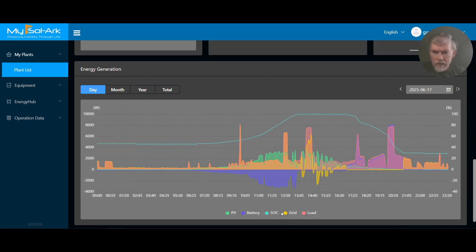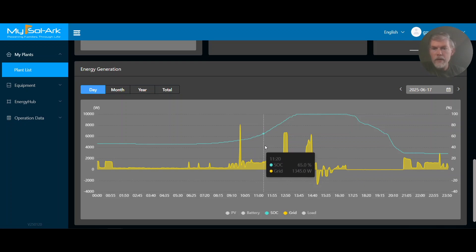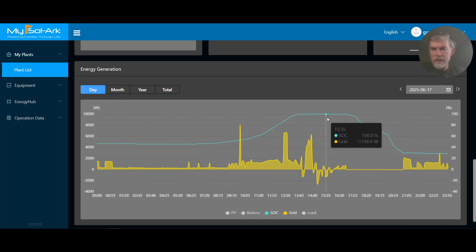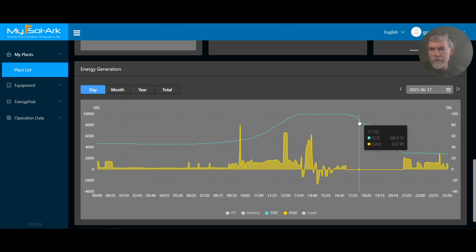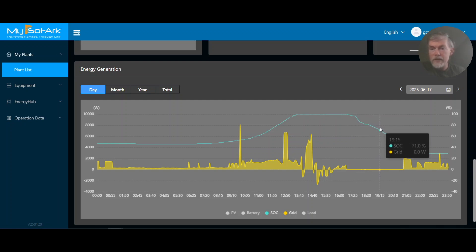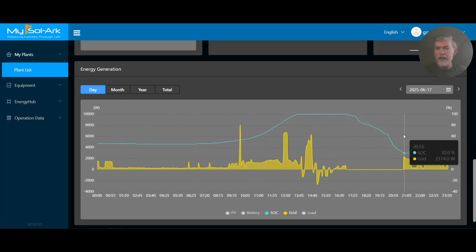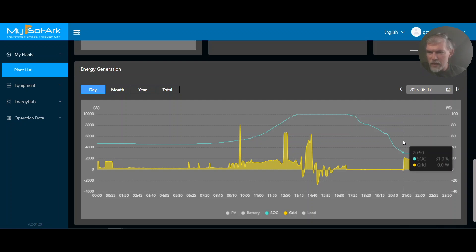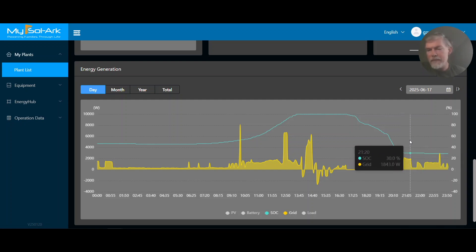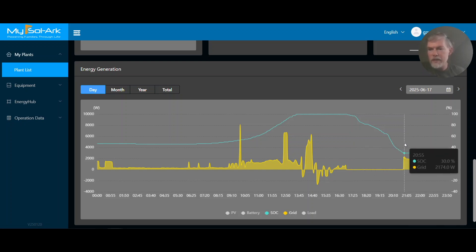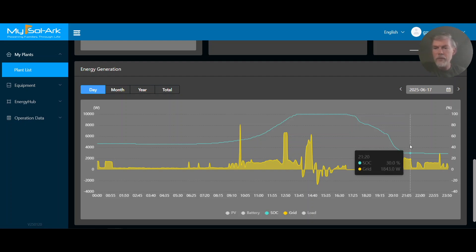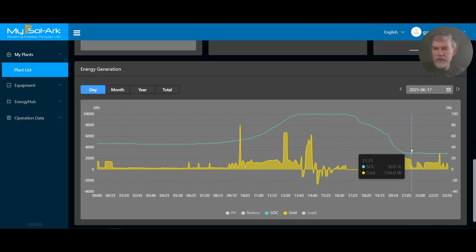Looking at the previous day, you can see the batteries got fully charged and sat fully charged for a long time. Then right at 3 p.m., we started to discharge the batteries to minimize the amount of energy used during that peak period — when energy is most expensive from the utility. We got down to 30% SOC, which is where the system is set to stop discharging. We made it all the way to 8 p.m. without using any grid energy, but by that point the batteries were nearly depleted and we had to use some grid energy. At least we're minimizing the amount pulled from the grid, and usually we're using less power later in the evening.